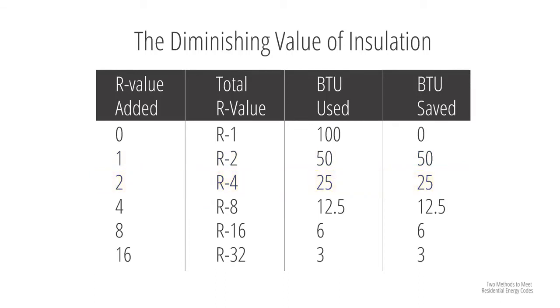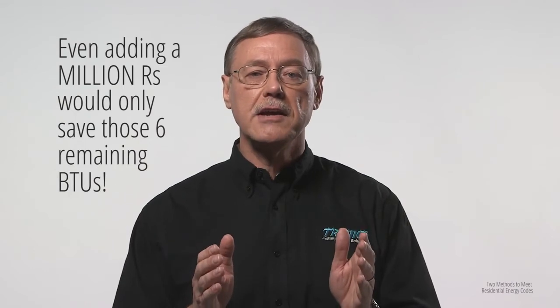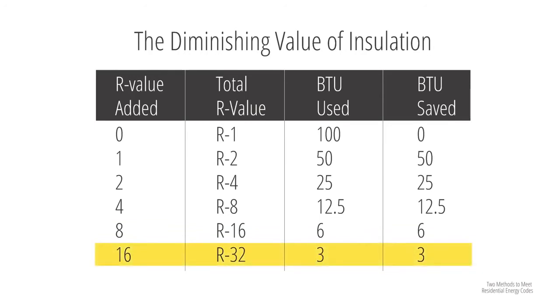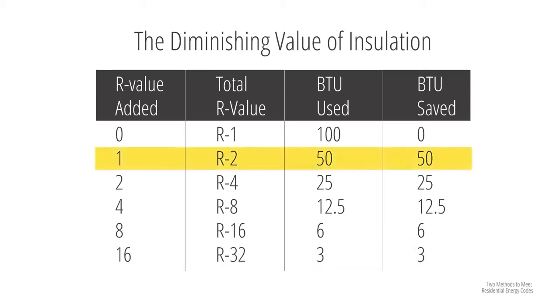Moving down to the next-to-last row of the table, where our system R is R16, we're only using six BTUs. Oddly enough, even if we had room to add a million R's in the attic, the only energy we could save would be those six BTUs — because you cannot save more than you're losing. Finally, if we double R16 to R32, we cut the six BTUs to three. So the first R we added saved 50, while the last 16 R's only saved three.